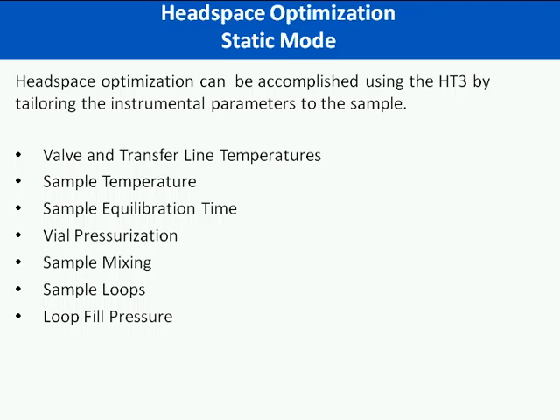The static headspace optimization can be used with the HT3 by tailoring the instrumental parameters to your sample. The HT3 offers the ability to tune your sample analysis by varying many of the instrument parameters. Those will include the valve and transfer line temperatures, the sample temperature which is your platen temperature, the sample equilibration time, vial pressurization, sample mixing, sample loops, and loop fill pressure.